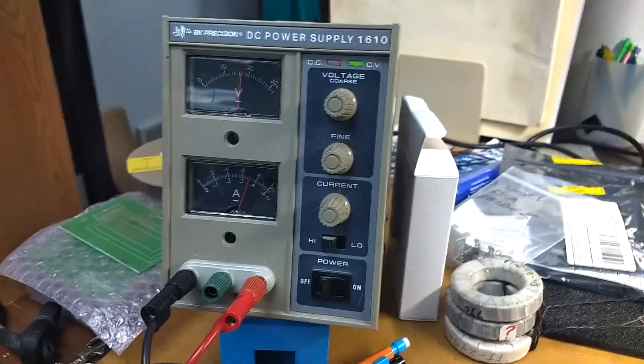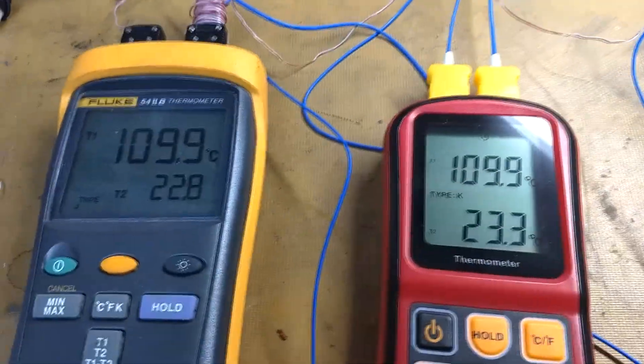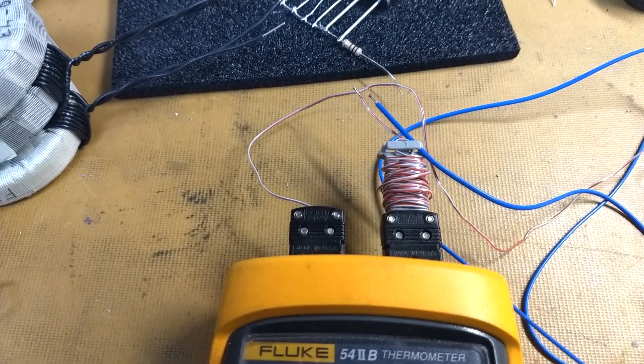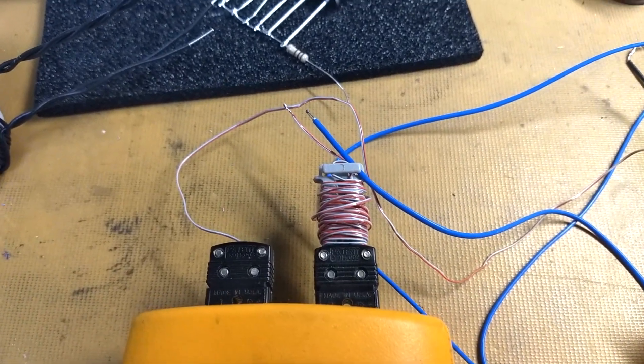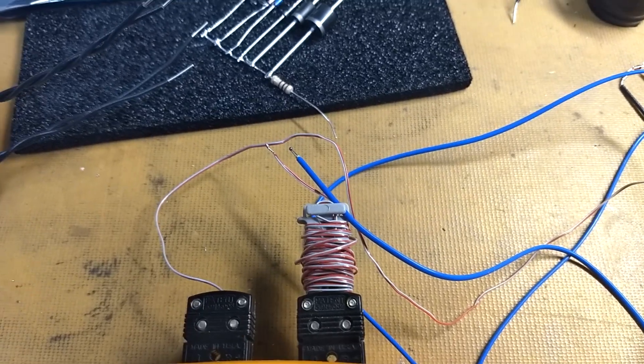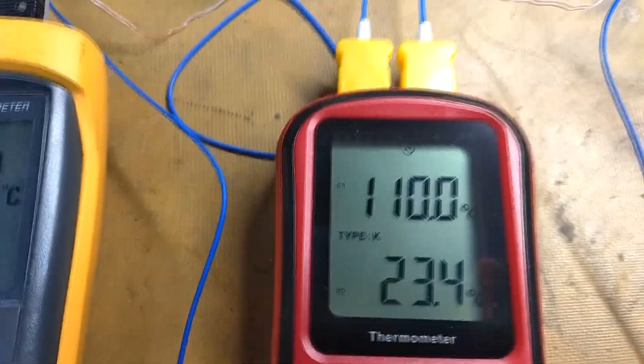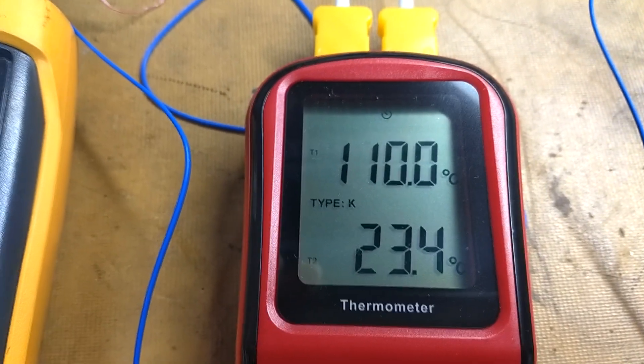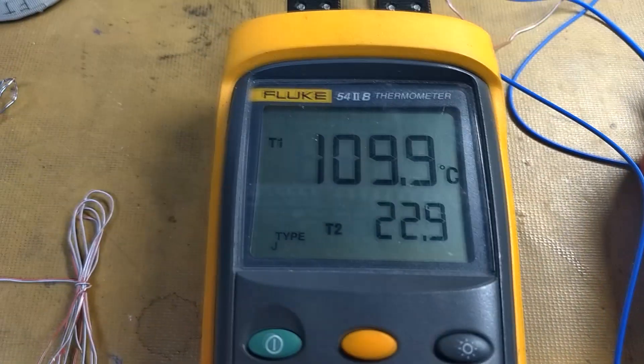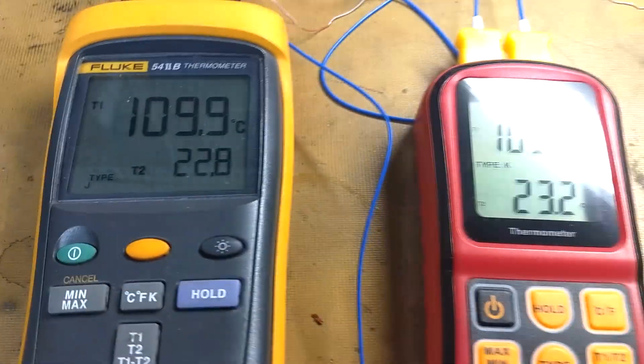We have a power supply here powering that resistor, and the two meters here. On this one we have the type J thermocouple running to that heat sink and one just sticking out here in the air for the ambient temperature. You can also see the blue thermocouple for the ambient reading for the other meter. This has been running for a while. This meter is showing 110 degrees on the heat sink with a 23.4 degree ambient, and this one is showing 109.9 with a 22.8 degree ambient. So they're very close.